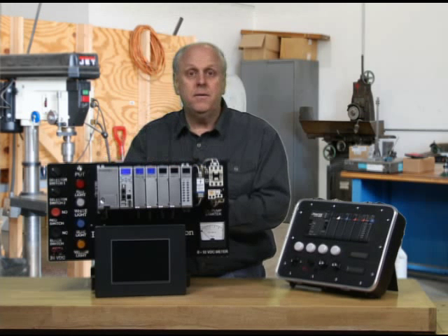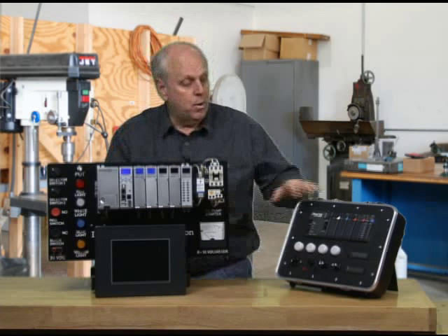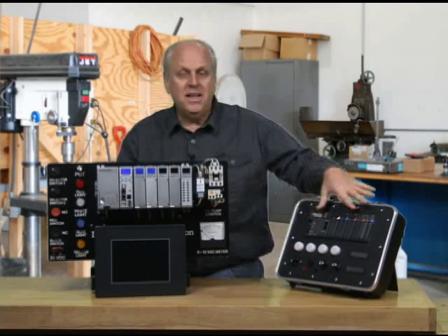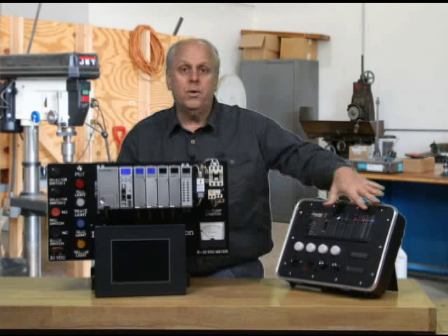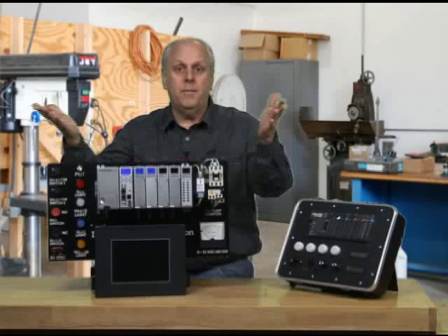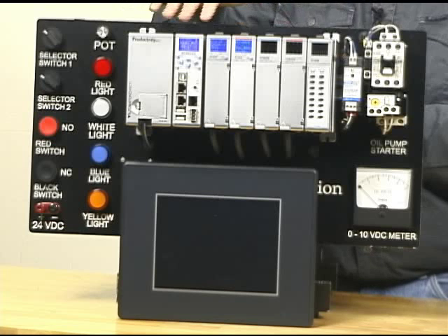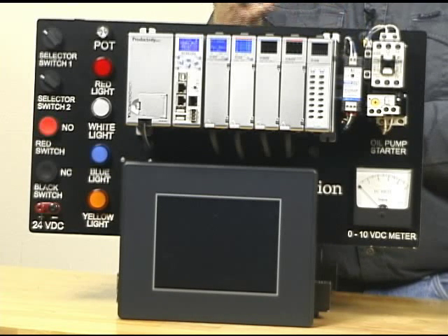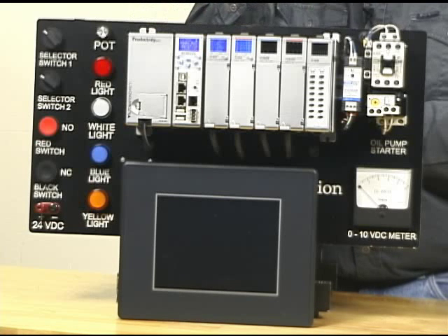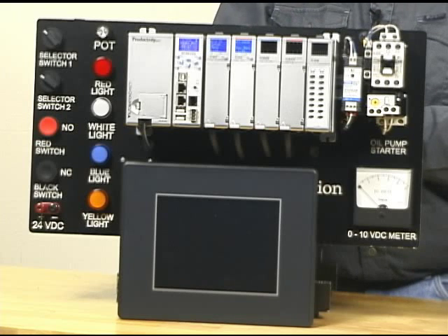Another nice feature, it auto-discovers all the hardware. Years ago, when we would use these units, if you plug things in, maybe the CPU, you had to address them yourself. Sometimes it auto-addressed them. Here, when you plug it in, it just automatically discovers everything. So if I put a remote rack somewhere else and plug it in, the CPU just automatically discovers it. And how does it do it? Well, it does it by itself, or you can click one button and say discover, or there's a third way. You can manually go in and say, I want these cards to be in these slots.